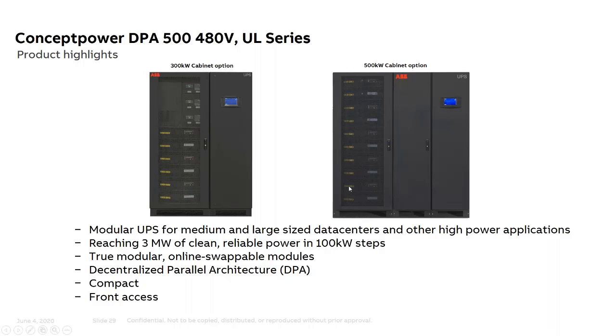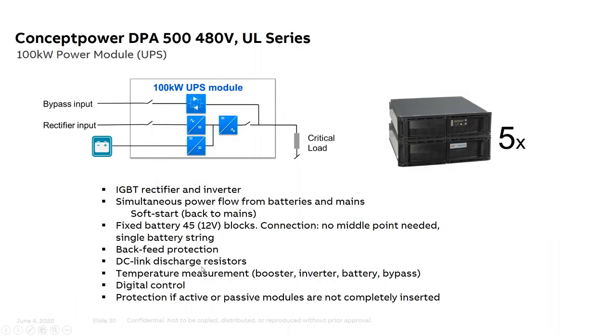We have the power modules sitting there. That's a 100 kW power module. So 5 of them will fit in the 500 kW, and it'll support 500 kW. The smaller one will fit up to 3 and support up to 300 kW. Or of course, with the 500 up, both of them. Actually, if the load is less than one less than the power modules installed, the unit will offer redundancy for the critical load. So this little thing here is actually a 100 kW UPS, same as the monolithic ones. It's an IGBT based rectifier and inverter. It's just a smaller one. And in the distributed power architecture, or DPA, UPSs, we just fit more of them.